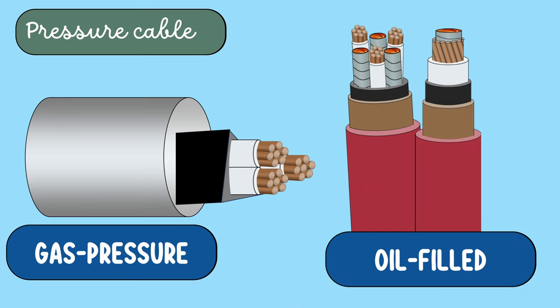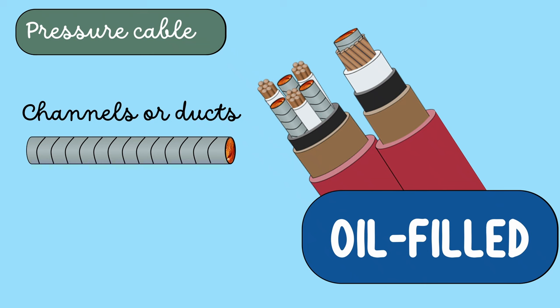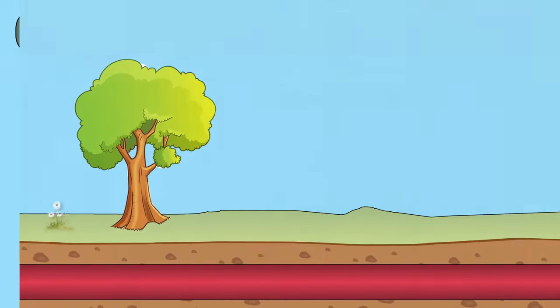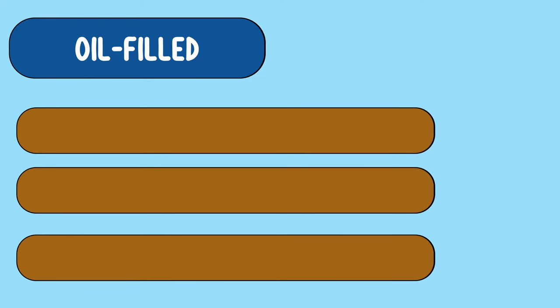Let's first concentrate on this oil-filled cable. Here, channels or ducts are provided in the cable for oil circulation. The oil is constantly supplied to the channel by means of external reservoirs placed at suitable distances along the cable route. The oil is maintained under pressure by these reservoirs. The oil-filled cables are classified into three types depending on the location of the oil channel in the cable.